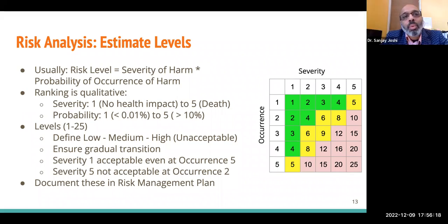Well, whose device it is, that's the first question. If the device is yours, then obviously you have done your bit to get it approved. Almost all governments are going to ask you to provide risk management of your device. So if the device is already approved, you can safely assume that the device itself has its own risk management file, and so on and so forth. Now, if that device is not made by you, it's made by somebody else, obviously you don't have access to their risk management file. You have to focus on the product that you are making.